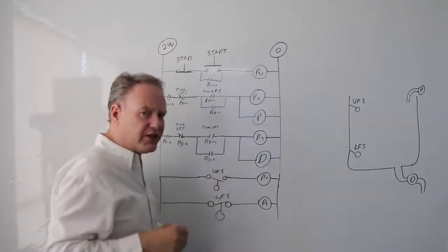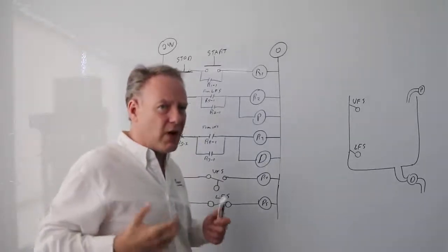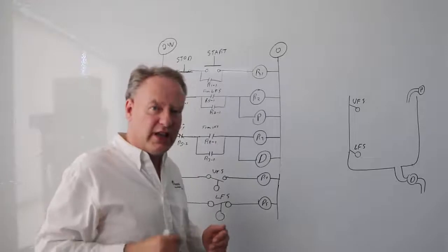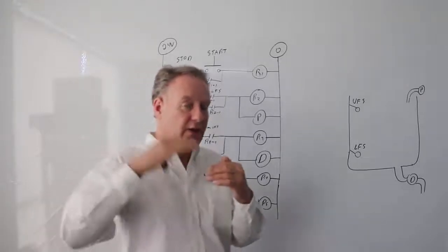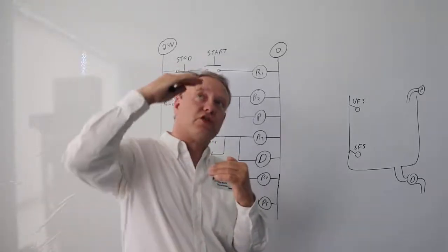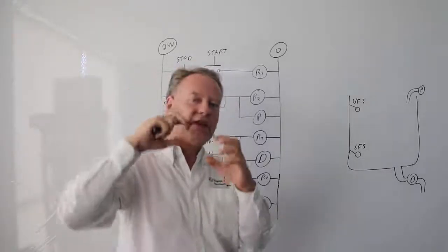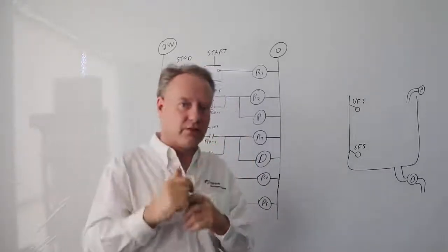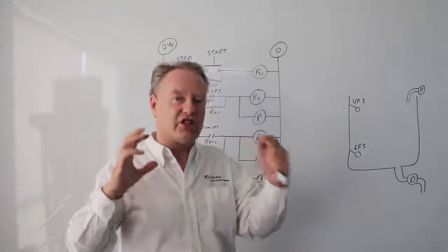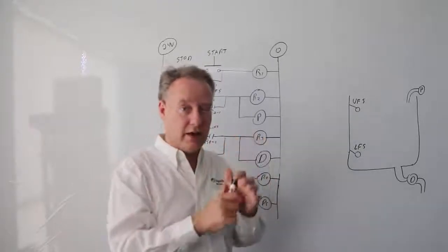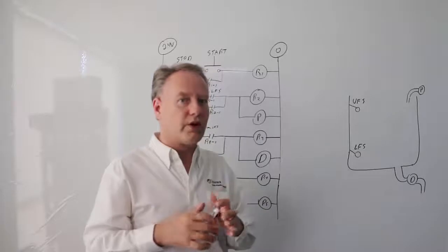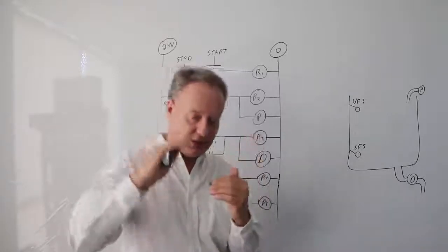Okay, let's continue on and look at the logic of how I make this thing stop if it's going. When I hit the stop, it continues all the way to the top, and then stops. So it doesn't turn the pump off right away. It leaves that pump on until it gets to the top, just like you're leaving the solenoid on until it gets all the way to the out. Also, we're going to leave that drain on until it gets all the way down to the bottom.